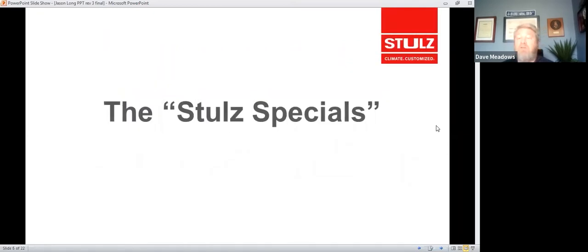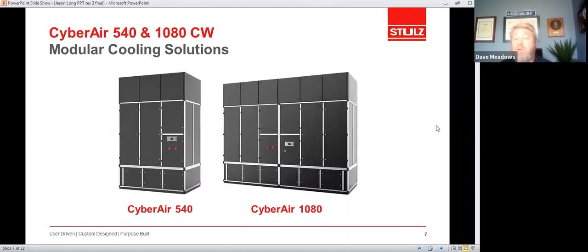So the real purpose today, and what Jason asked me to speak on, was some of the non-traditional data center, computer room, and telecom space units that Stulz currently provides to the North American market. I want to start out with our modular cooling solutions. These are chilled water units, computer room air handlers. The Cyberair 540 is currently designed to provide about 45,000 CFM, and at ASHRAE Class 2 return air conditions, about 500 kW of cooling per unit. So that equates to roughly 145 tons of cooling.